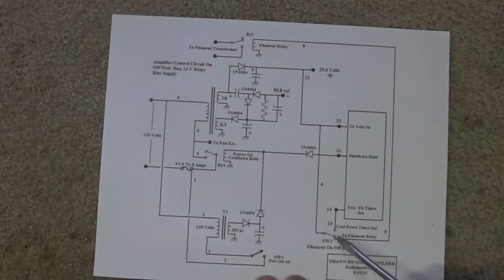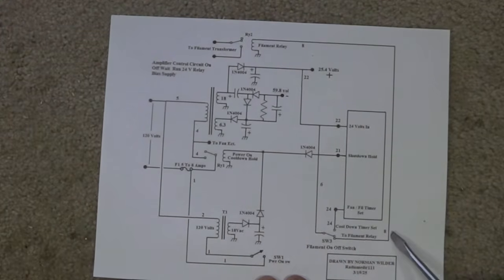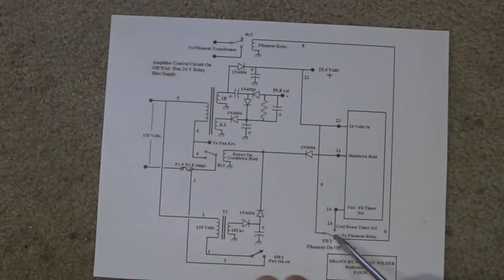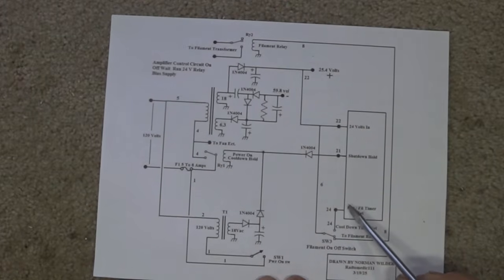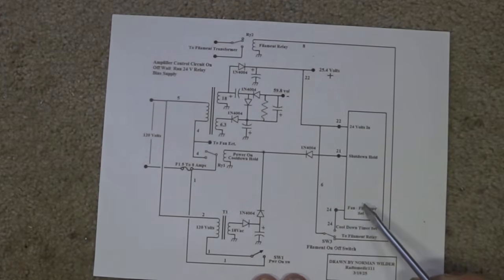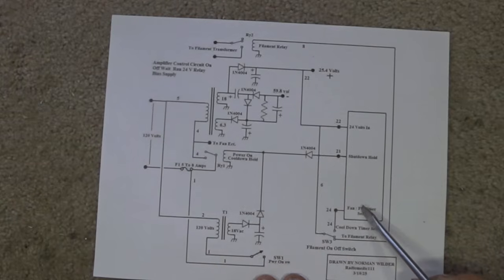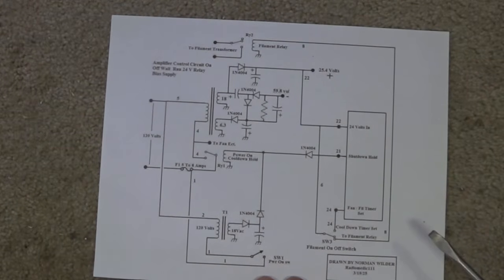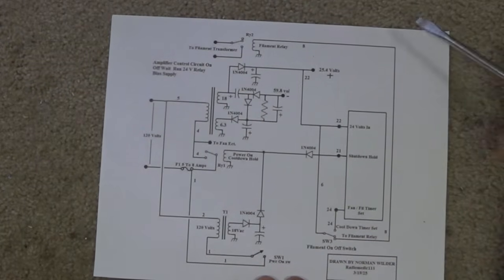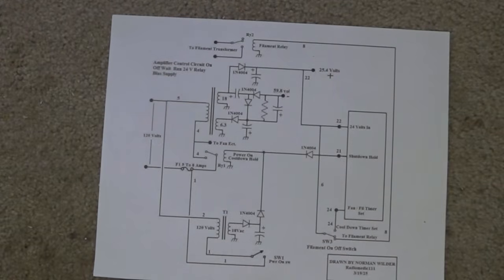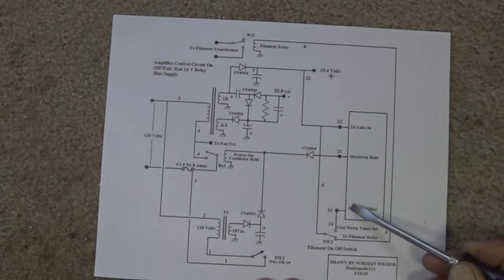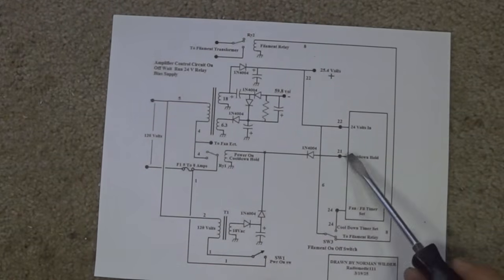So this turns the filament on, and if we wanted to turn the filament off for cool down, this switch then would move to here. That activates that circuit I was just showing you, that activates and charges those caps, holds the relay closed, starts the fan timer. And since we've moved this switch to turn the filaments off, now the tube can cool down, but yet the circuit will hold the power supply on.